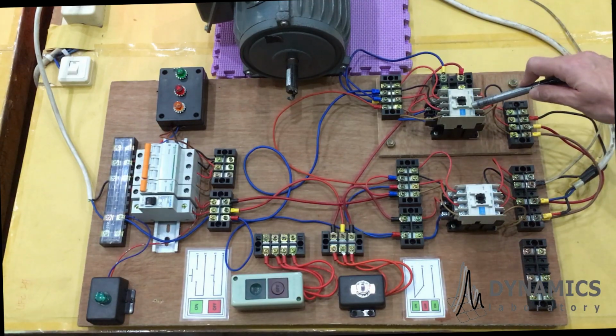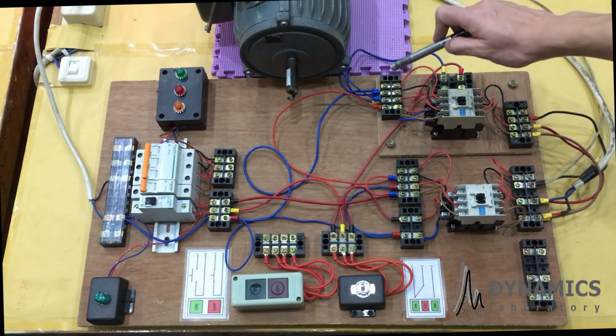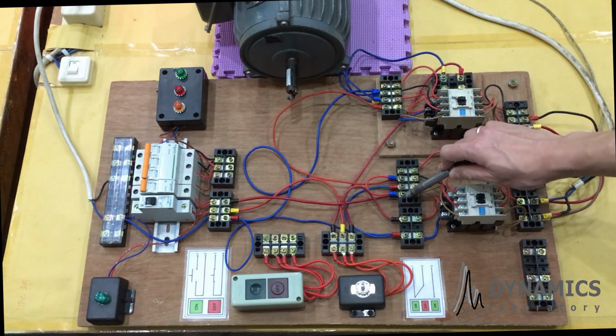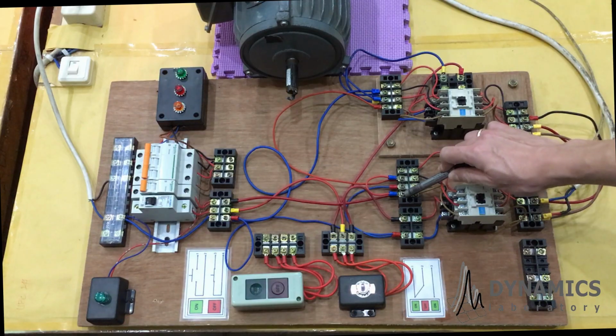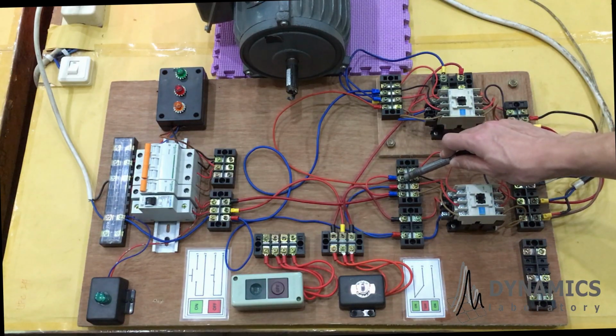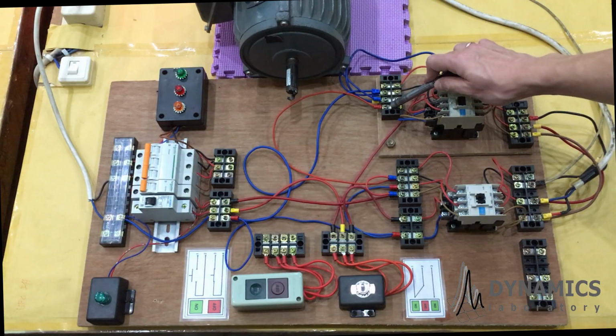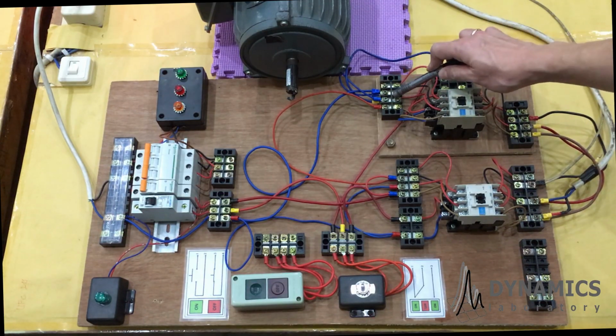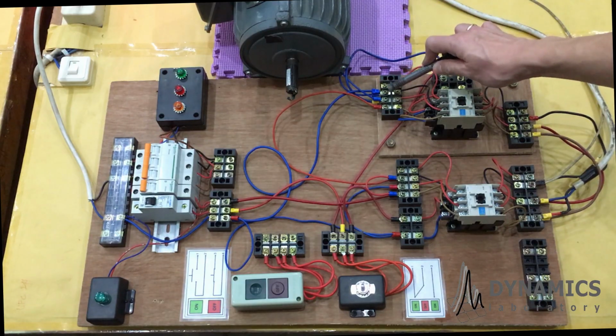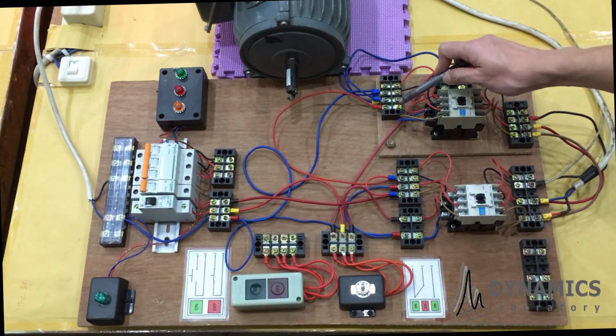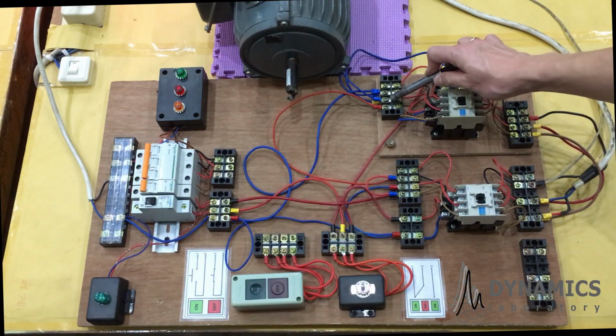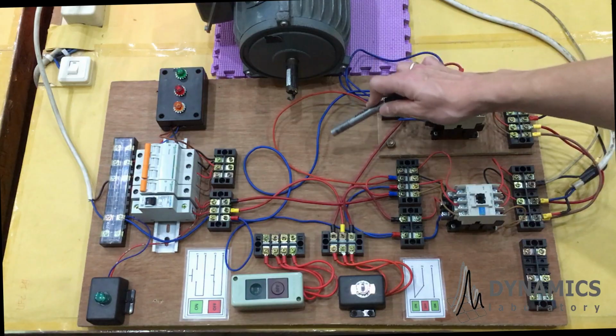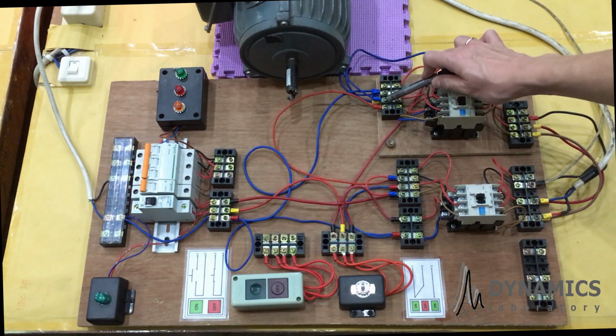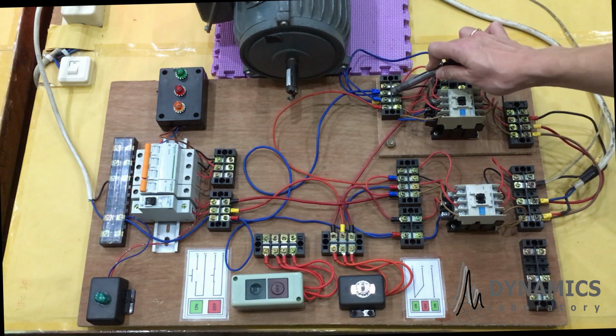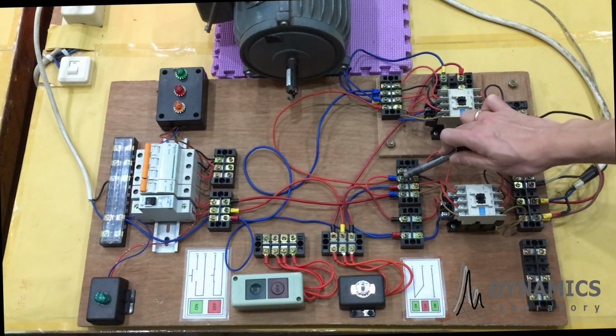And then for contactor 2, just see the sequence. The sequence in here is red cable main winding, blue cable main winding, and auxiliary winding. And you see in here is the same. Main winding red cable, main winding blue cable, and then auxiliary winding. And as you can see in here, the main winding is the same. Red cable gets live terminal, blue cable gets neutral, but pay attention in here. Auxiliary winding is different from contactor 1.